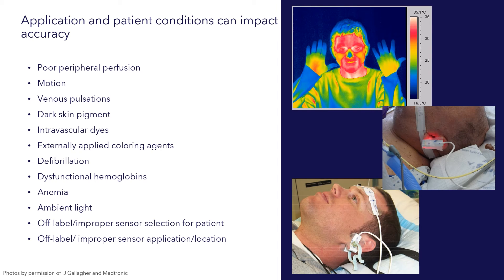Excessive motion can also interfere with the readings of the pulse oximeter. When we look at peripheral perfusion as well as motion, it might be important to consider using a different location other than the digit or ears, or areas where low perfusion may be, to a sensor that measures the supraorbital arteries, such as a reflectance sensor, which may be more accurate in low perfusion conditions.